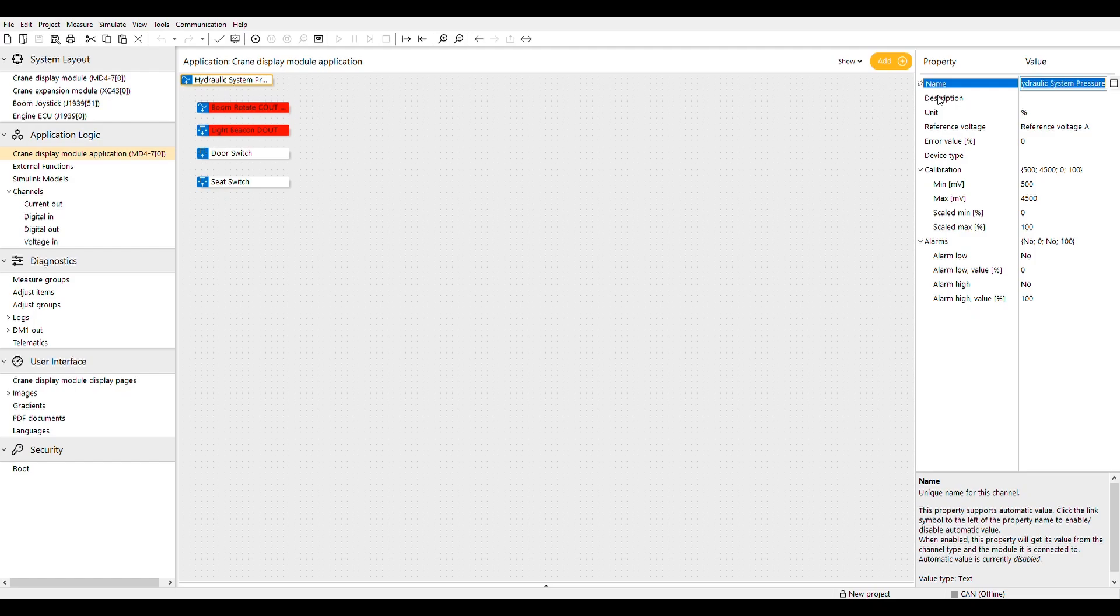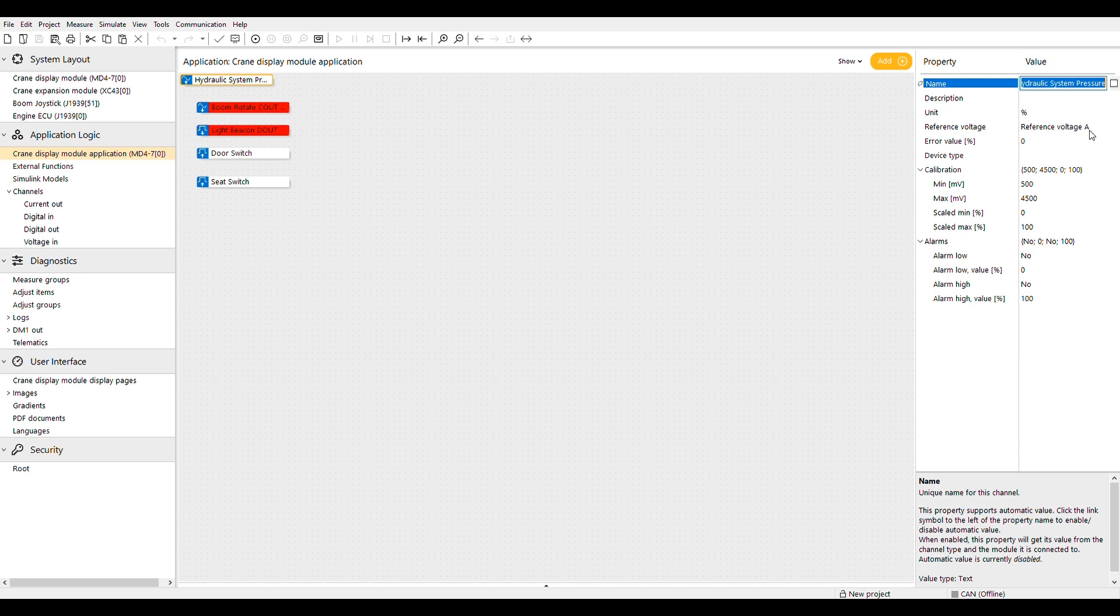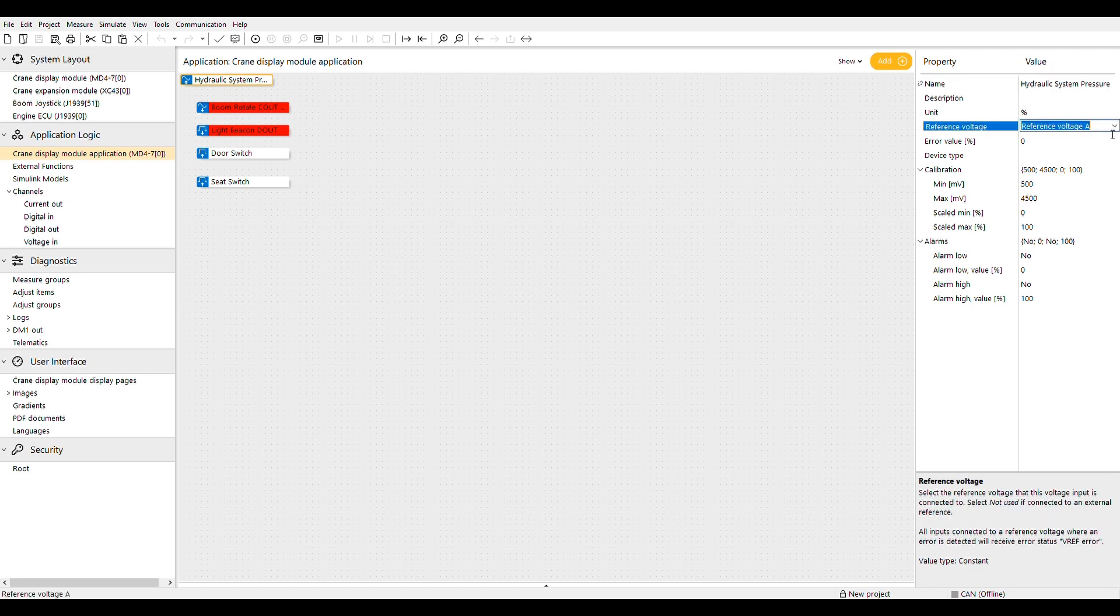The reference voltage lets you choose one of two built-in 5-volt regulated reference voltages to power your sensor, or you can choose not used if you are supplying external power. Using the built-in VREF will provide an error warning if an error is detected. The error value is the value that would be used if an error was detected.